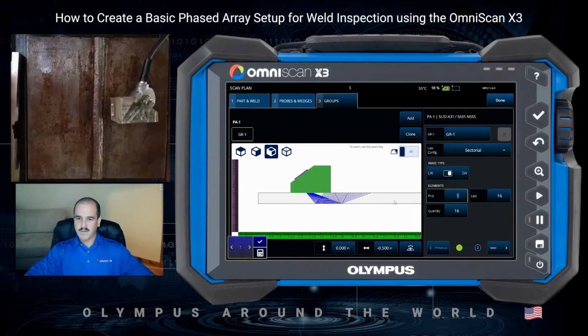And we're going to bump our first element up so we can try to get that first leg to cover that root while utilizing the second leg to cover that near side bevel as well as the volume of the weld. So we can use our scroll wheel here to push the elements forward a bit. And it looks like a start element 12 will give us a good coverage of that root in the first leg as well as the bevel and heat affected zone.